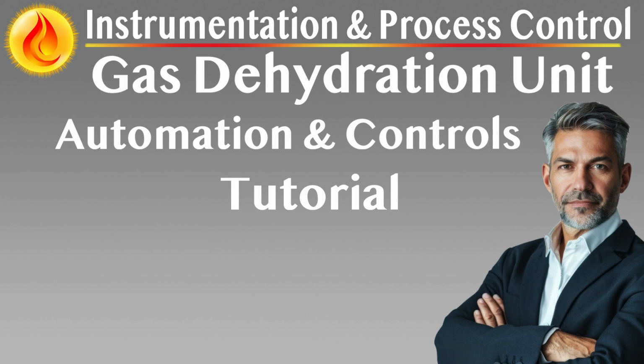Foam detection and entrainment prevention. Demister pad monitoring. Differential pressure transmitter, DPT, across the demister mat provides early warning of clogging or foam-induced entrainment. Entrainment can be inferred from excessive differential pressure and elevated glycol loss downstream. Top of contactor temperature and pressure. RTD and PT at the dry gas outlet provide validation of dehydration efficiency and detect temperature excursions that may indicate hydrocarbon condensation or loss of control.